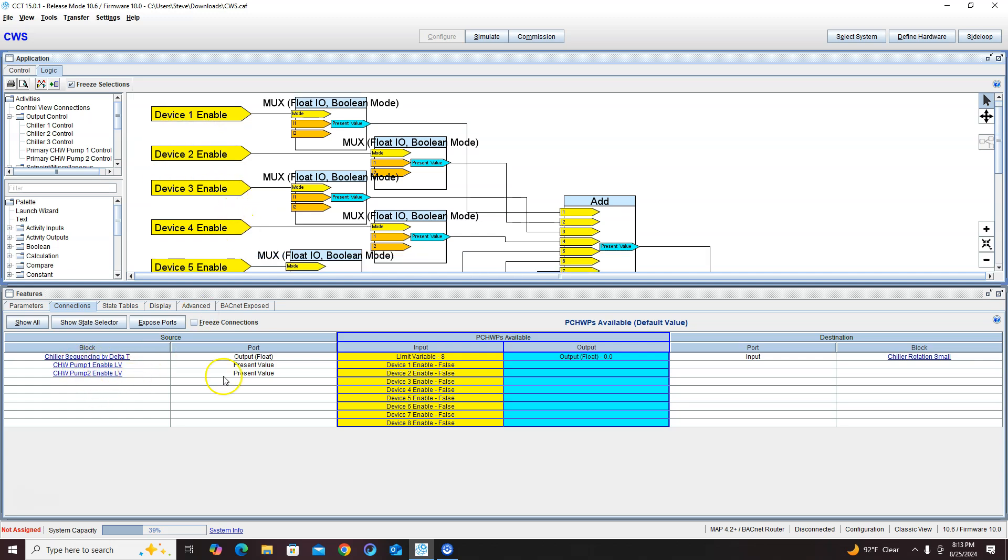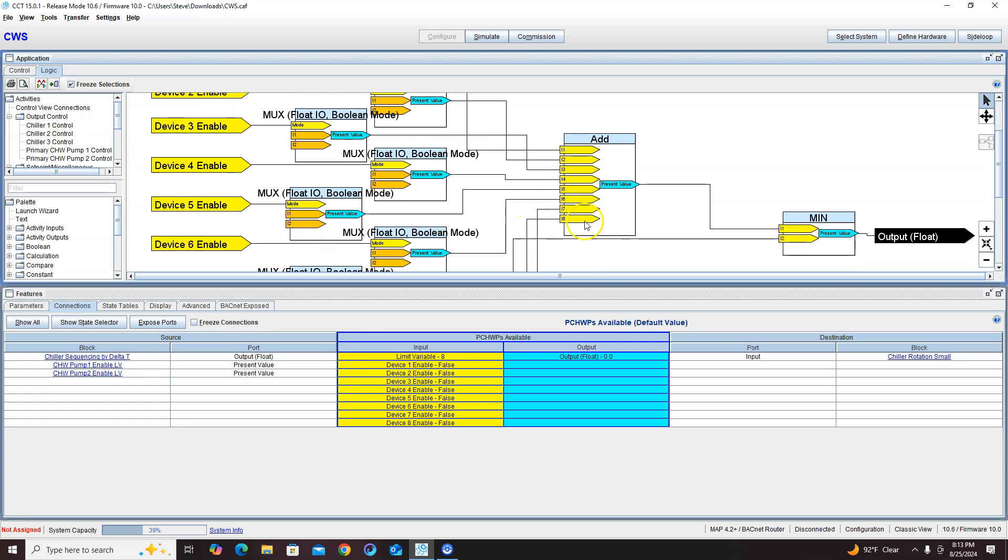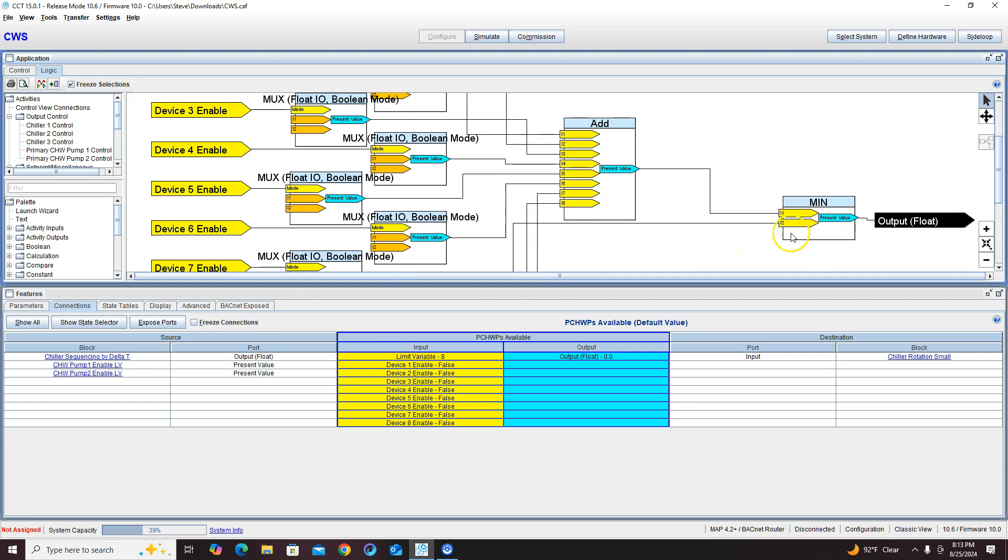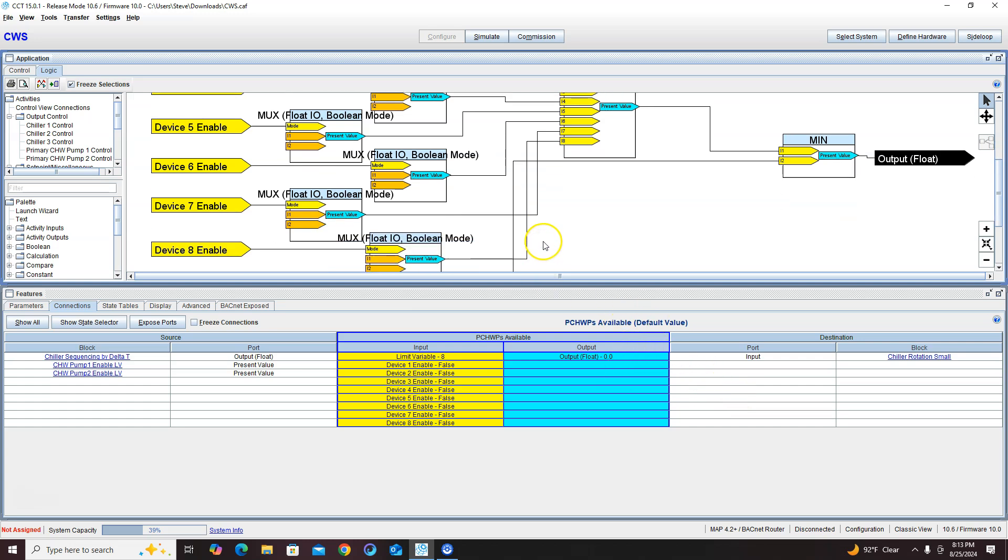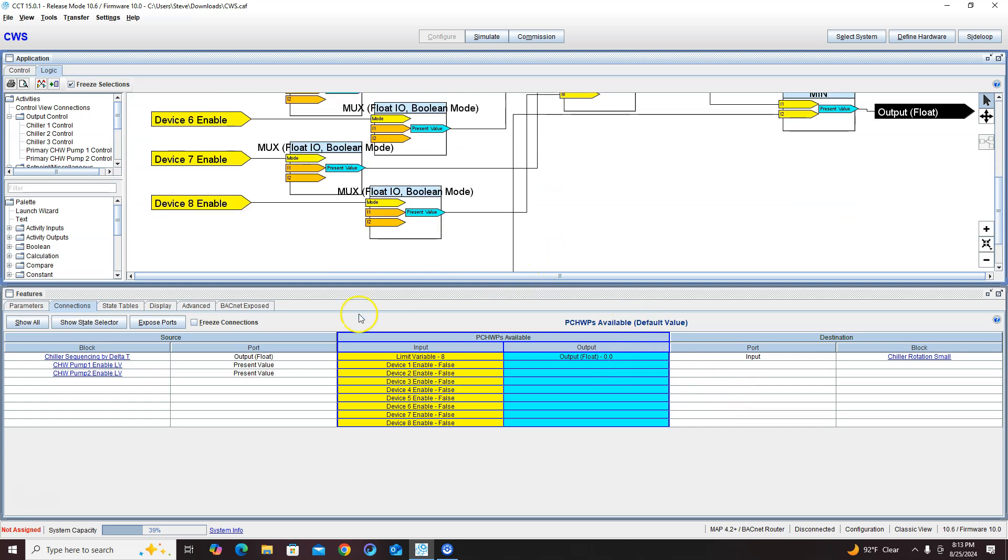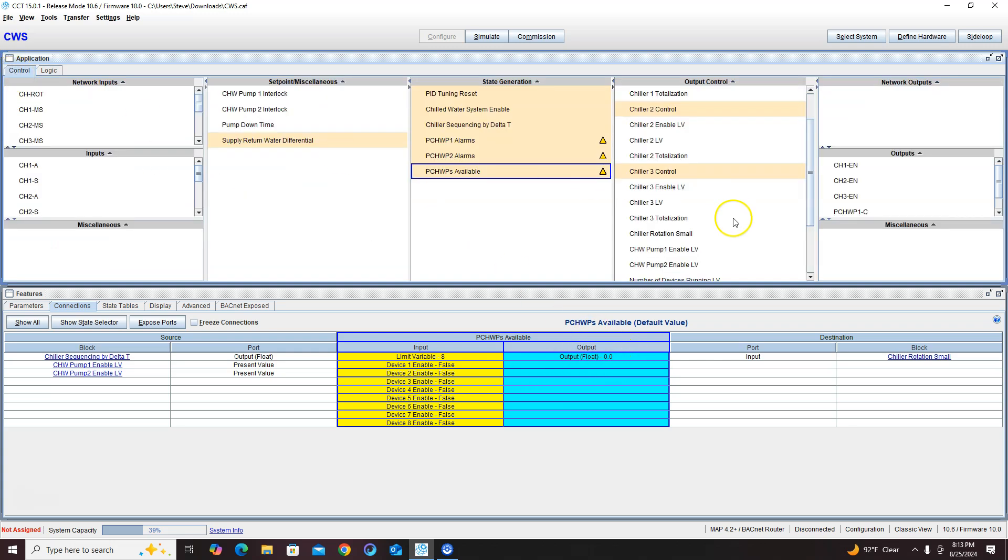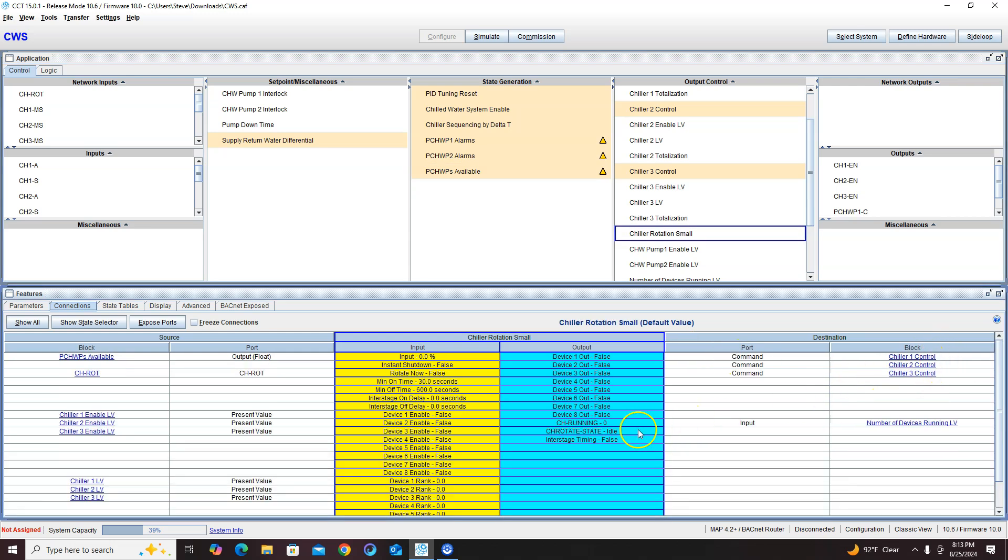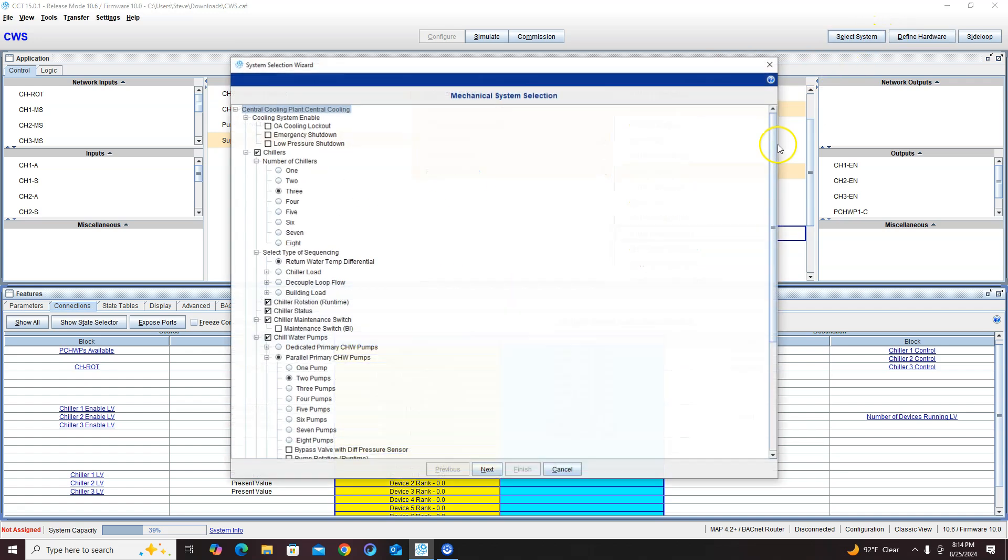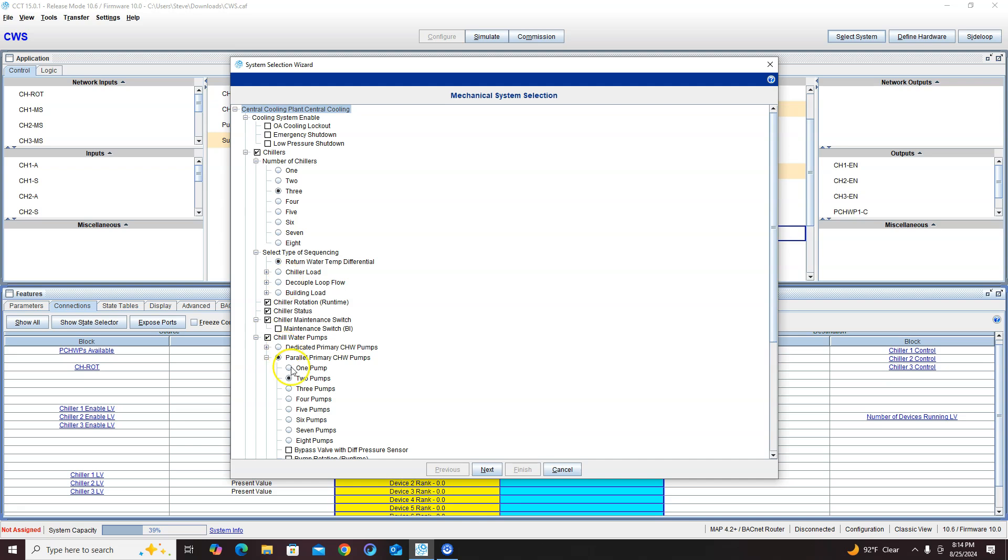Inside, it's only looking at these devices enable which is only gonna be these first two right here, and you're gonna get your minimum right here as your output. So even though we might have a three coming in here, will never have more than three coming out here, which actually goes into your chiller rotation small, which means it's only gonna look at the device rank and only turn on the two chillers for that.